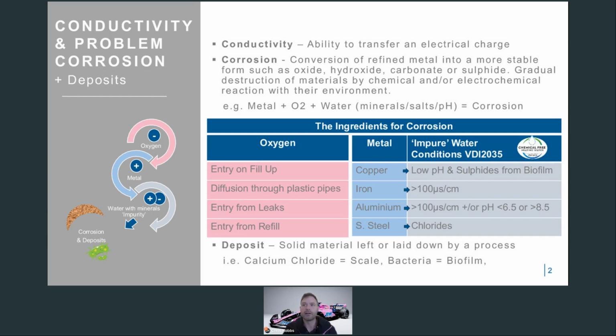This can be further accelerated as the metals have their own particular vulnerabilities that can be exploited with a third thing, which is impure water conditions. These conditions are listed on the far right. So when the heating water is, for example, too conductive, containing dissolved minerals with differing electrical charges, this accelerates the corrosion, the impure water acting like a medium of exchange. And you can see there are many vulnerabilities listed, but mostly the water should be under 100 microsiemens of conductivity and within 1.5 degrees of pH 7.